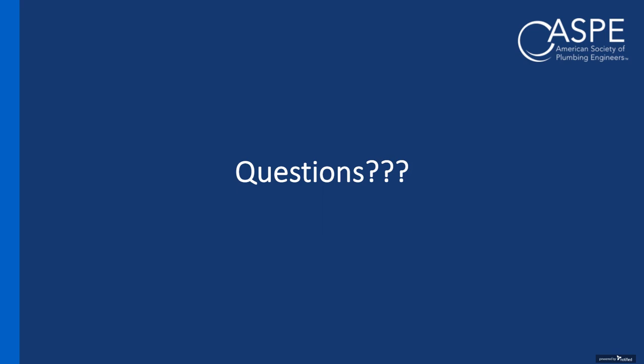Great. Next question. Do you need aquastats to energize the recirc pump, and where would you locate them? So that's a good question. We get that a lot. I think there are codes, we're changing in some areas now, but that require aquastats. Thermostatic balancing valves don't require aquastats to work properly. And especially if you combine a thermostatic balancing valve with a variable speed pump, then that will slow down the flow to where it needs to be to overcome the heat loss.